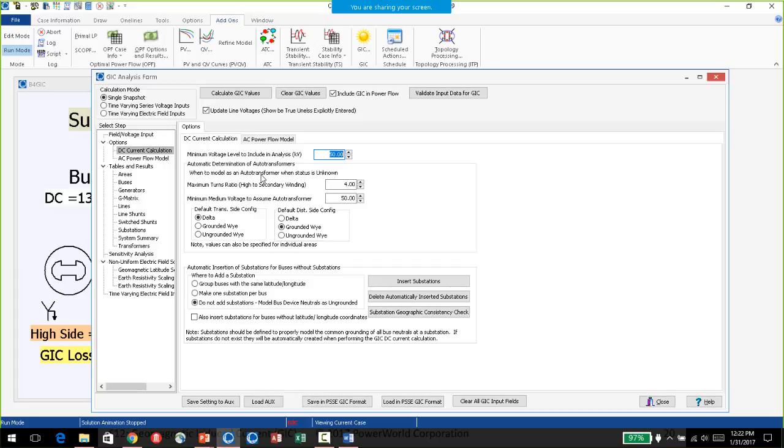If that's the case, then you're really simplifying your life if you just look at 500 kV and above, because you might have tens of substations. If you start looking at the lower levels, now you've got hundreds or thousands of substations. And some of it was based on what Louis Marti did at Ontario Hydro. So it might have worked for their system, but not your system.